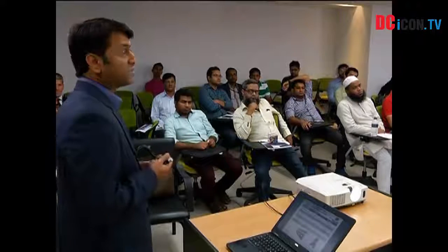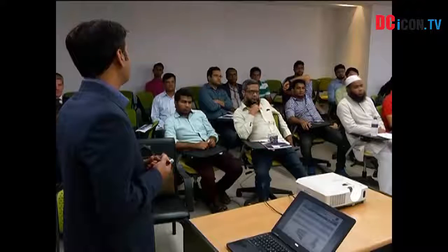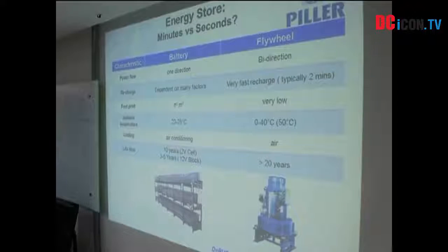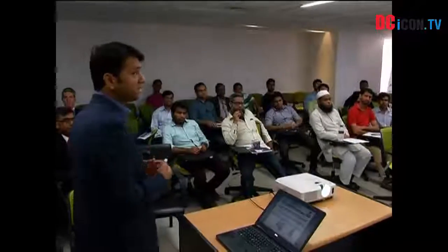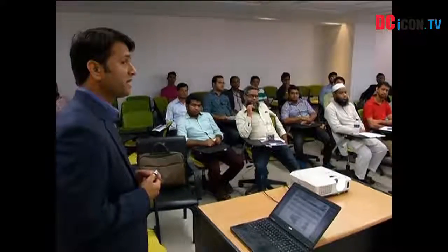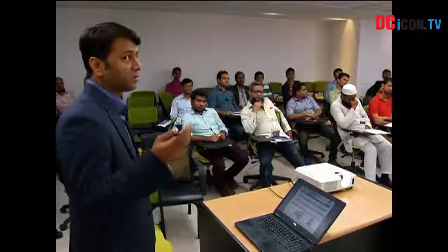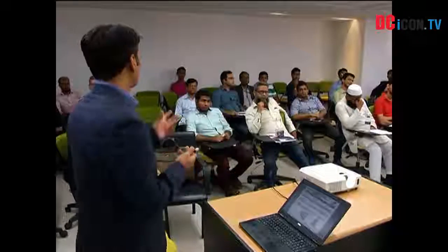The recharge time is typically less than 2 minutes, 2 or 3 minutes, and within that duration, the flywheel is automatically recharged back. So you don't need to worry about the number of failures. You can handle many failures. The footprint is very small. We are talking about very low footprint, so you save a lot of space in your data center or other applications in terms of energy storage.